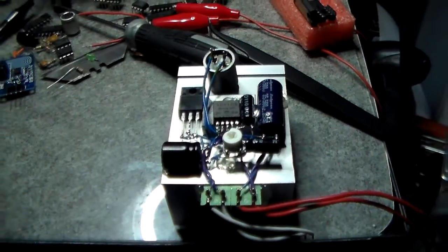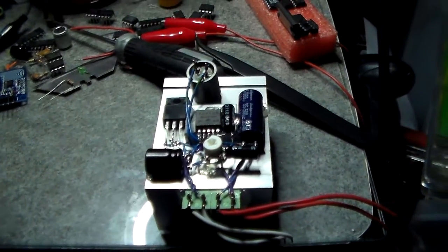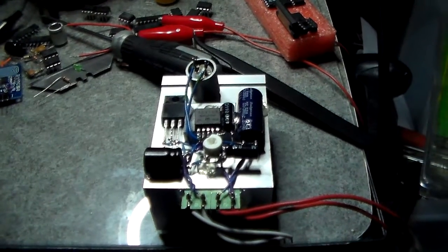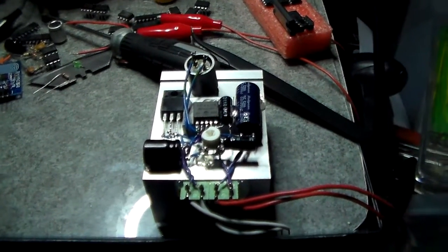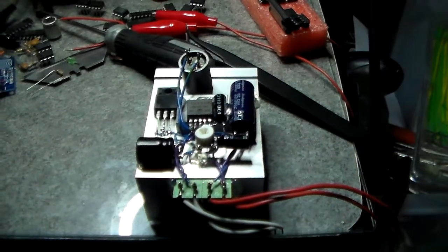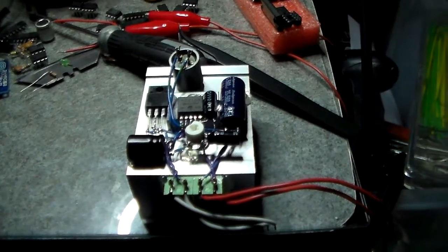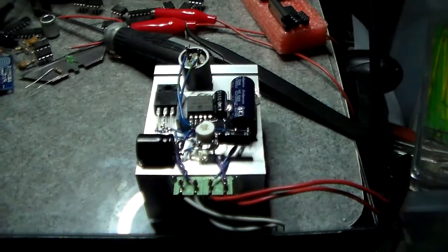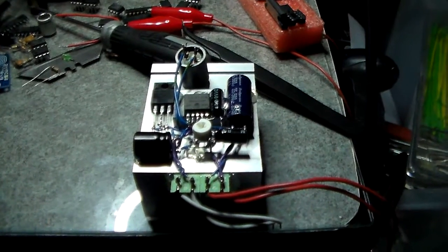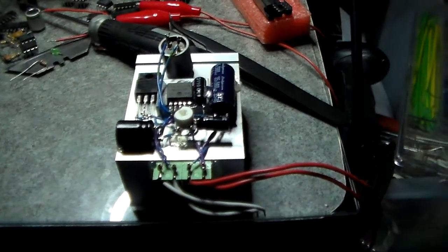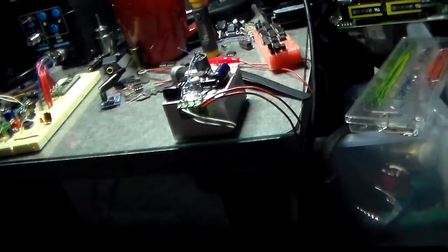So where if you remove the voltage and put it back, basically in a brownout scenario, it will latch its output, so it'll give the main output to its output. That isn't very good. I'm gonna have to see whether it does that all the time, or what are the actual scenarios of that.